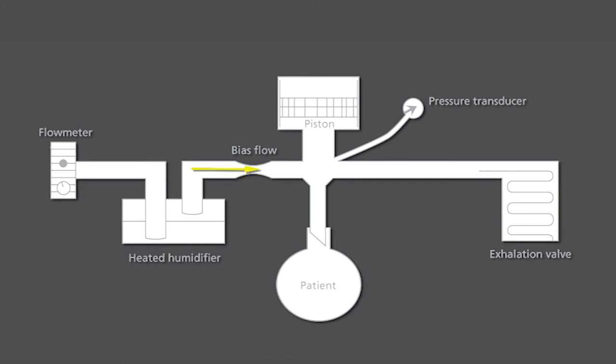The gas then continues through the circuit to the patient and then out through the exhalation valve. The variable restriction to the outflow of gas generates mean airway pressure while the piston superimposes the ventilatory process.